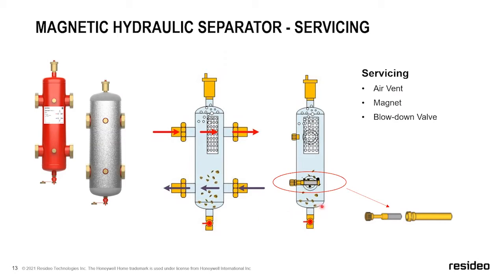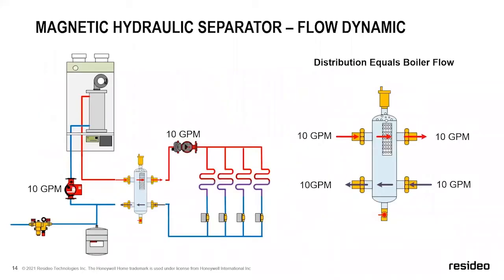You're only basically looking to drain this segment of water out, but you may lose a pound or two when you do that. Screw the magnet back in and turn the pump back on. That's pretty much all you have to do. Very, very simplistic from a servicing standpoint on this. And I wanted to kind of go through what the reason for using one is, some of the different operational criteria you'll run up against.